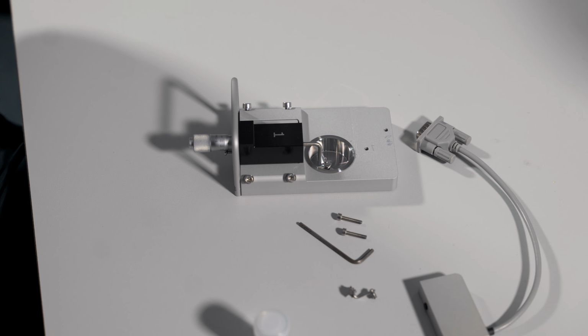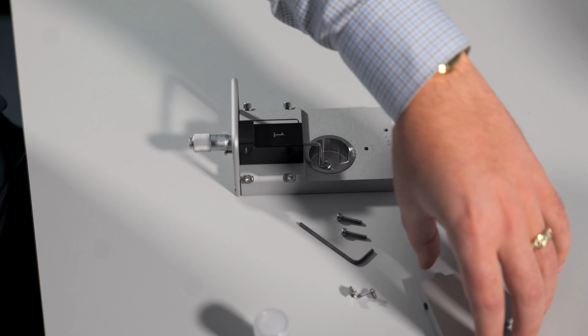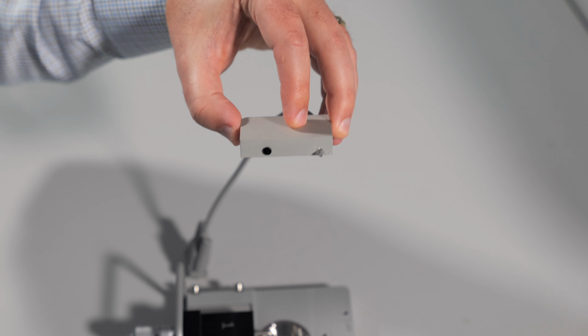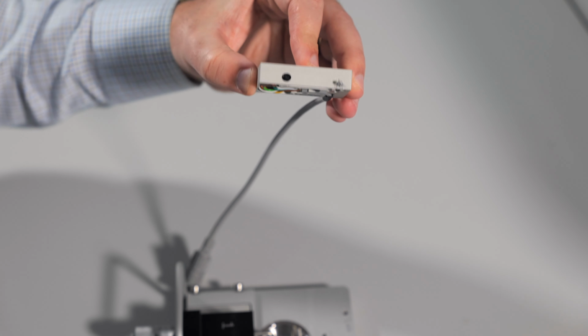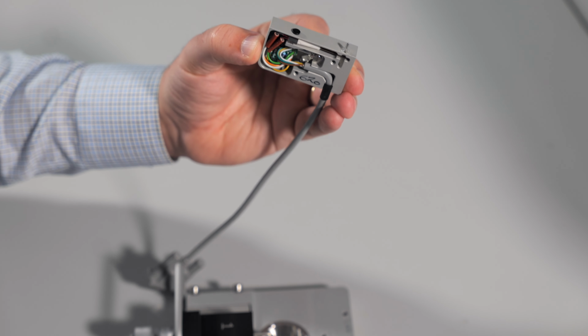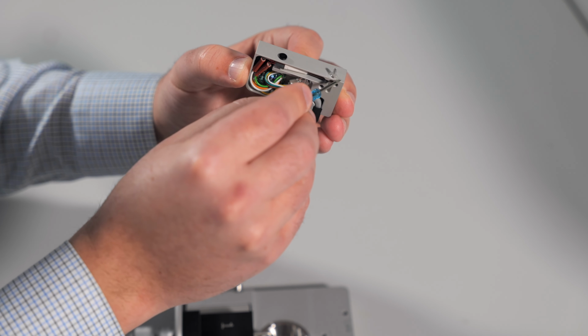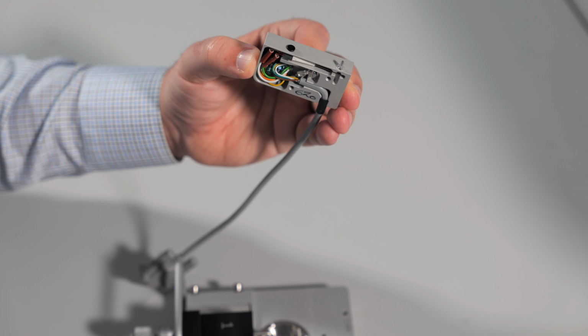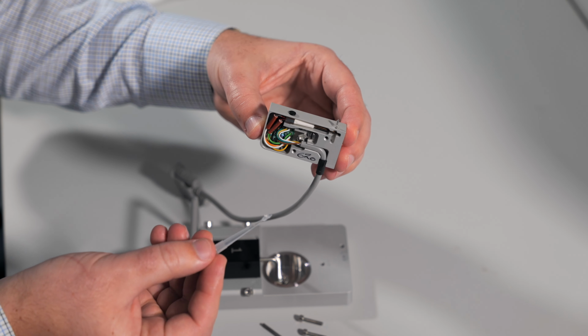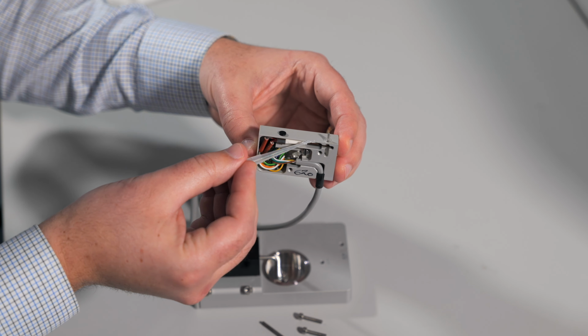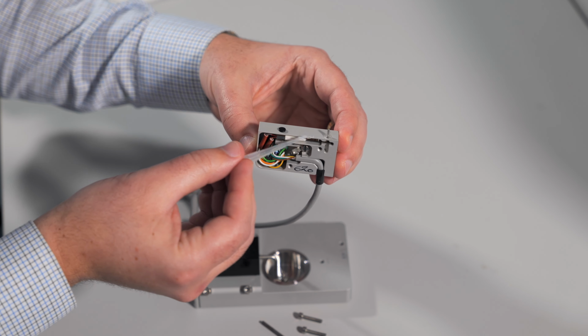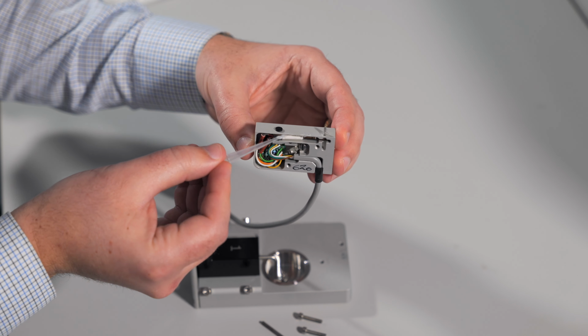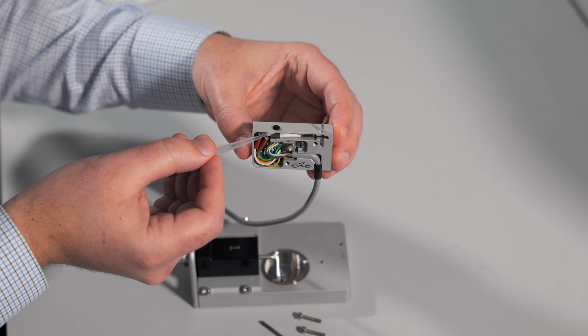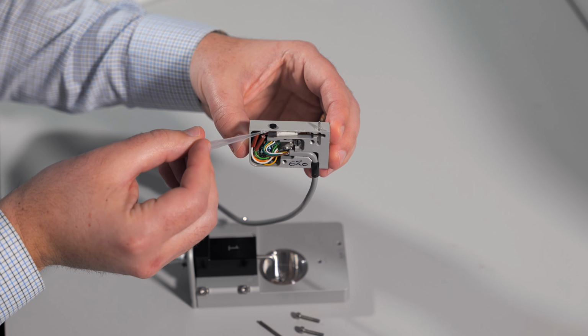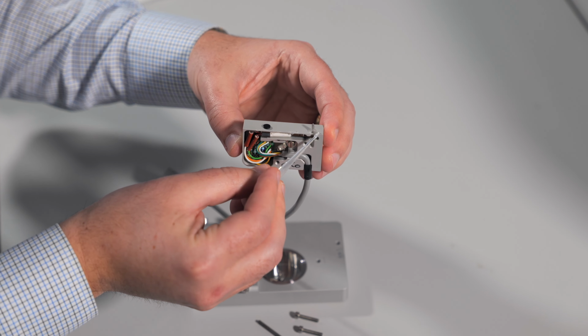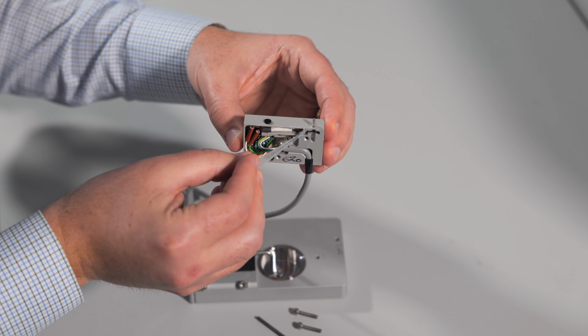To prepare the replacement transducer for the chamber, you want to make sure that it's properly greased. You can see here that this transducer has been greased already, but if it is not, you will take either a pipette tip or a 1 ml syringe and apply some of the clear silicone-based grease around that pinhole. It is also a good idea to add grease along the front edge of the transducer. This will protect against any liquid entering the transducer housing. You can take your pipette tip with grease and apply it along this edge.